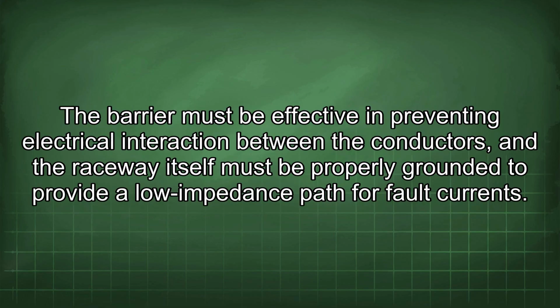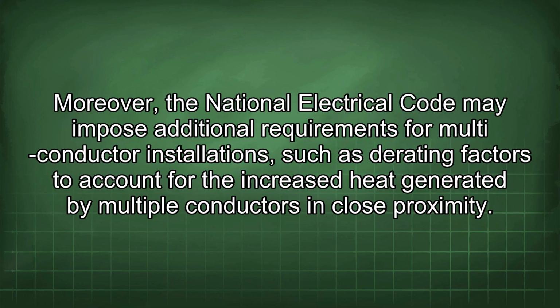The barrier must be effective in preventing electrical interaction between the conductors, and the raceway itself must be properly grounded to provide a low impedance path for fault currents. Moreover, the National Electrical Code may impose additional requirements for multi-conductor installations, such as derating factors to account for the increased heat generated by multiple conductors in close proximity.